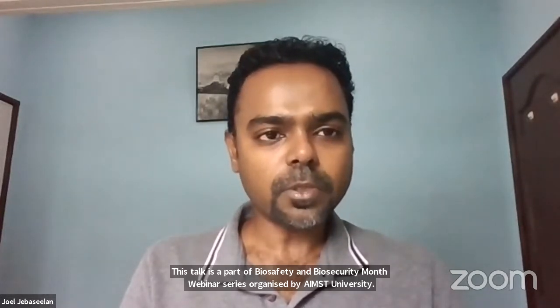So two things: one is what they need to do within the biosafety cabinet and what agents they're going to use, that's the risk assessment. And then what the facility can handle, whether it's within a BSL-3 lab or BSL-2 lab, which decides whether the air should be treated or not, and how much of the air is treated. The variety of biosafety cabinets, whether 30%, 70%, or 100% of the air is treated, again falls back to the risk assessment and the type of agent being used.